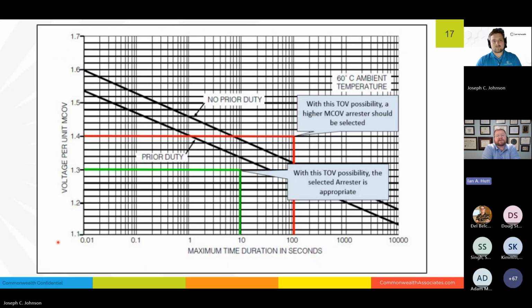You'll also notice on this graph that there are two different curves. One is for new arrestors without any duty. This is what you might expect during testing phases when we're looking at new equipment. However, we have to understand that these devices, as they work, as they take more and more strikes, they degrade. As that degradation happens, we have that classified as the prior duty line that we're seeing there. So you'll notice that as long as your protection is guaranteed within a certain window of time, in our green box here, a per unit MCOV of 1.3 is allowed, and that'll work even after these devices have seen a fair amount of action.